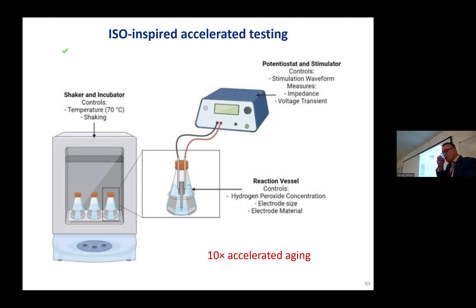So to learn how this works, we set up ISO-inspired accelerated testing where we take implants, we put them in media that are spiked with peroxide to simulate the reactive environment that is caused by implantation. We heat the media up to 70 degrees. That gives you approximately 10x acceleration in terms of time. And we also move the stage to simulate micro motions. And then put different types of implants and run them until they die.